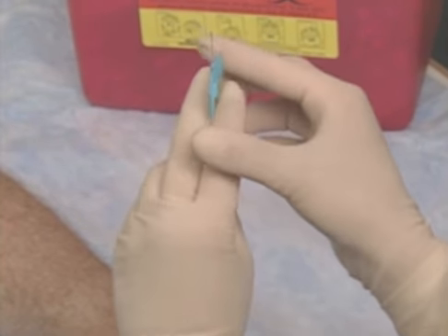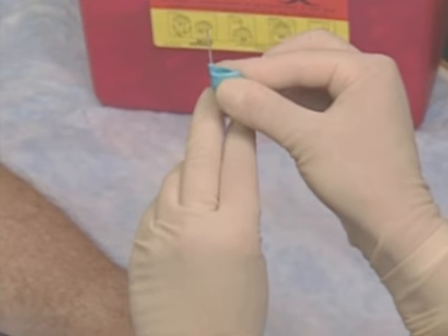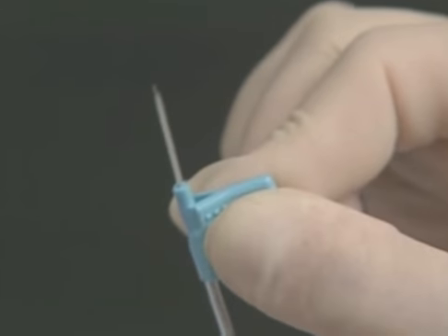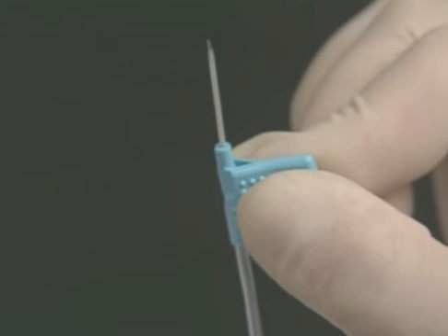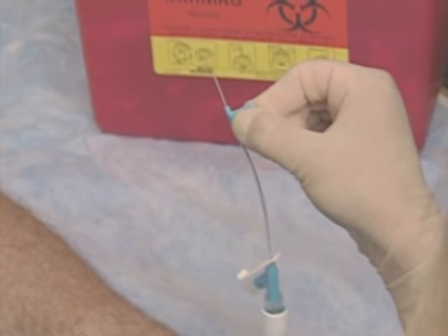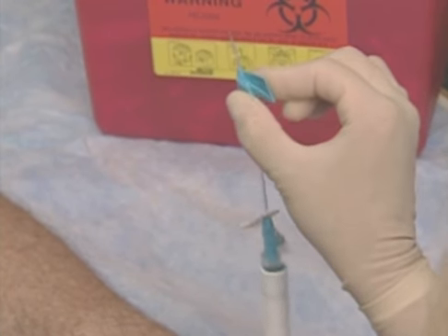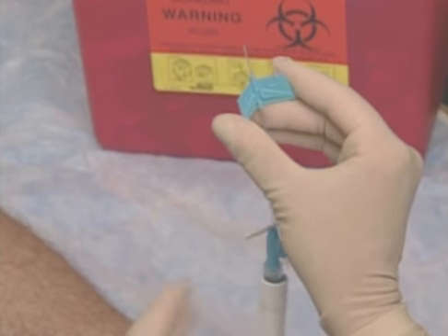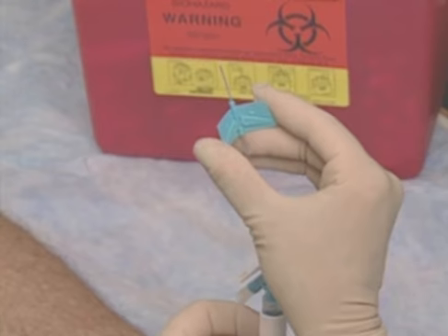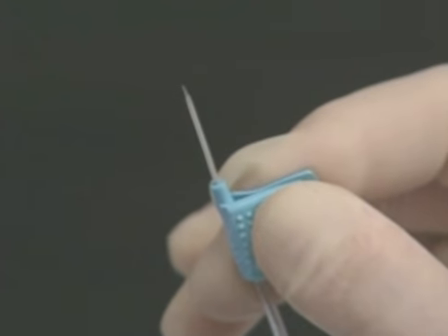Grasp the wings and firmly pinch them together. Your finger should be touching the pebbled side of the wings. It's imperative to pinch firmly, otherwise the needle will push back into the catheter when you attempt to penetrate the skin. This situation could cause increased insertion pain for the patient. If it becomes necessary to reorient the needle bevel, relax your grip and twist the safety shield until the bevel is facing upward, and firmly pinch the wings again.